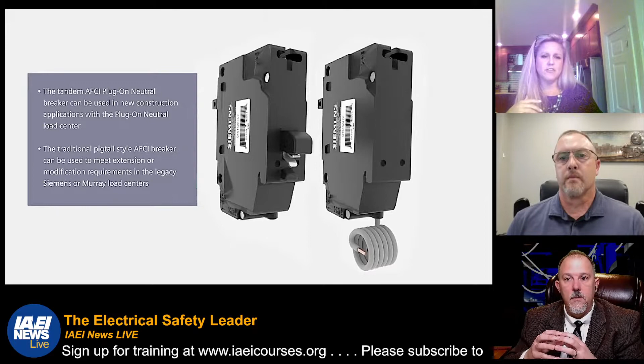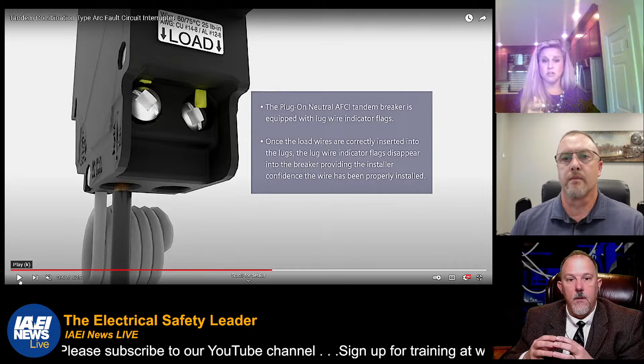And if you're doing any type of renovation, the pigtail breaker is going to be really good for those legacy panels. And as you know, if you are adding on any circuits and your panel's already full, what a pain to have to add a sub panel. But now you don't have to do that anymore. You can just get yourself a couple of these tandem breakers, take out your single poles, add in your tandems. Now you've got some extra circuits, and you don't have to add a sub panel.